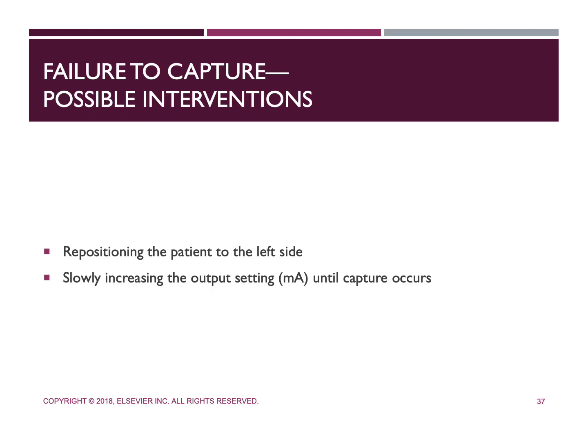So if the problem is a result of low output energy, slowly increasing the output energy until capture occurs may resolve the problem, which just means that the setting that it's set at might be too low. They might have to make it higher. With transvenous pacing, repositioning the patient to the left side may promote the contact of the transvenous pacing lead with the endocardium and septum.